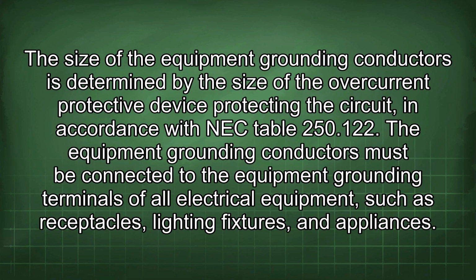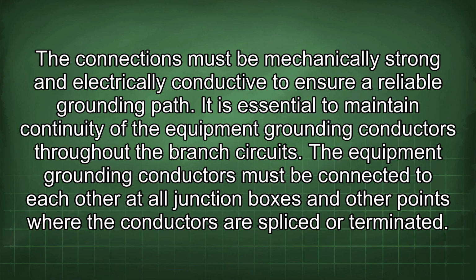The size of the equipment grounding conductors is determined by the size of the overcurrent protective device protecting the circuit, in accordance with NEC Table 250.122. The equipment grounding conductors must be connected to the equipment grounding terminals of all electrical equipment, such as receptacles, lighting fixtures, and appliances. The connections must be mechanically strong and electrically conductive to ensure a reliable grounding path.